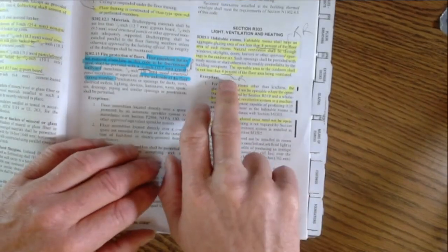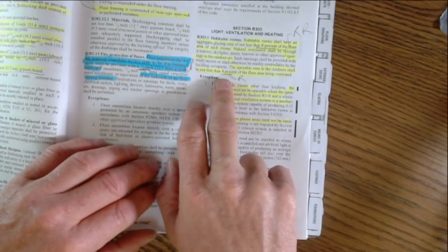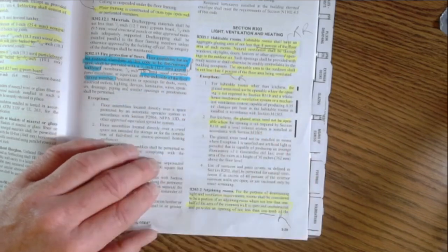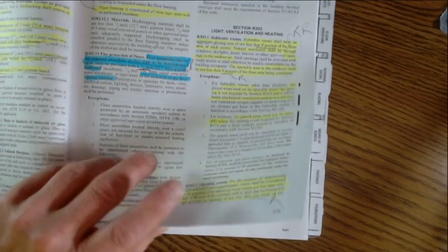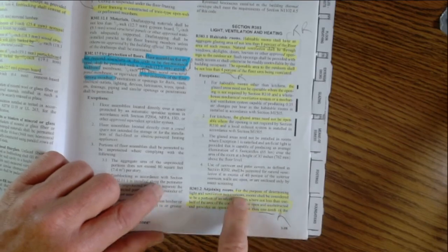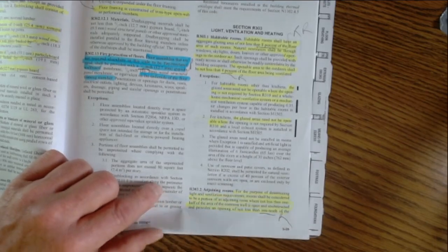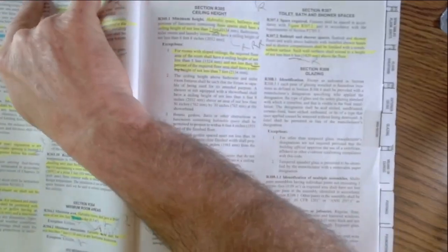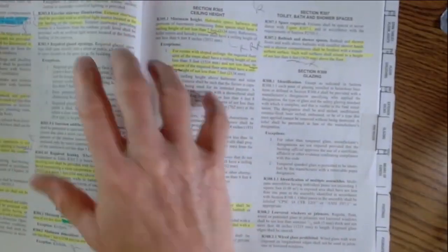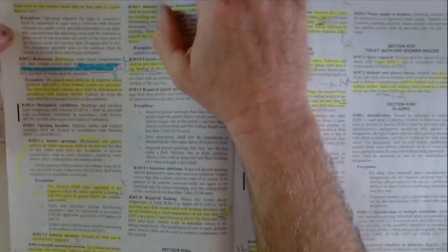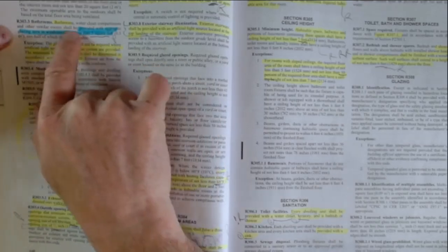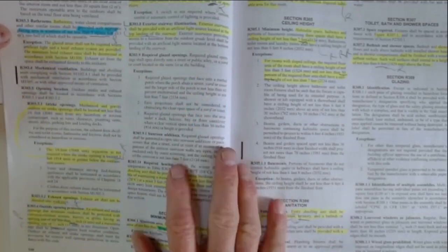If you're relying on natural ventilation, you need 4%. So if you have a 100 square foot room, it's 4 square feet. Adjoining rooms, know this. This is important. If you have a room that's not vented, there's an allowance for you to use either 1/10. Anyway, I'm not going to go into details, but know what that is, because that's the exemption. This is the bathroom section. You can use 3 square feet here.